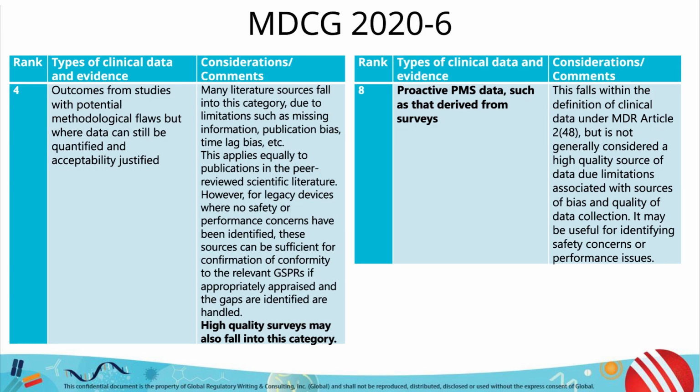In particular, rank 4 and rank 8 include types of clinical data that are directly relevant to PMCF surveys. High quality surveys that are appropriately designed to address device unknowns can constitute evidence rank 4. General surveys can support PMS data collection activities and serve as general PMCF data.